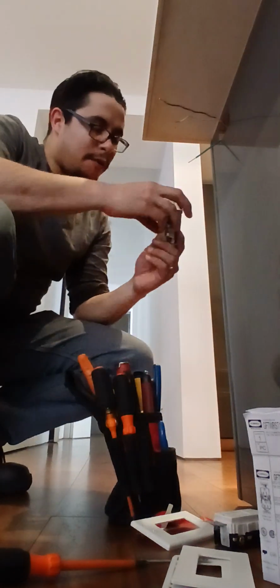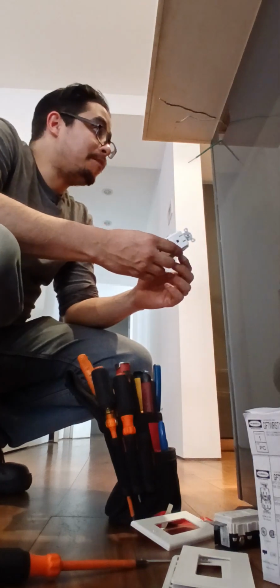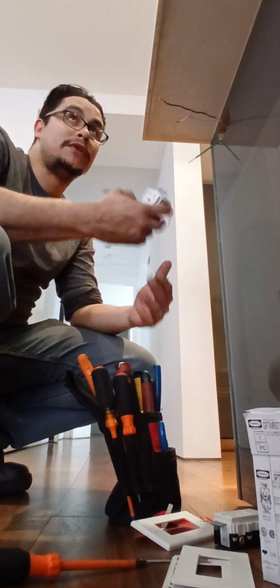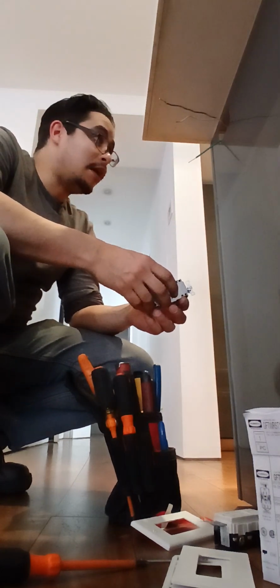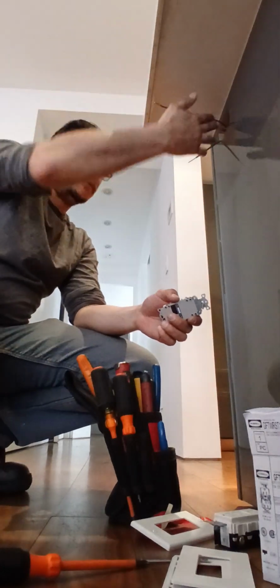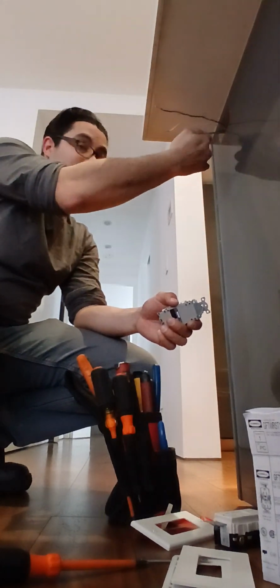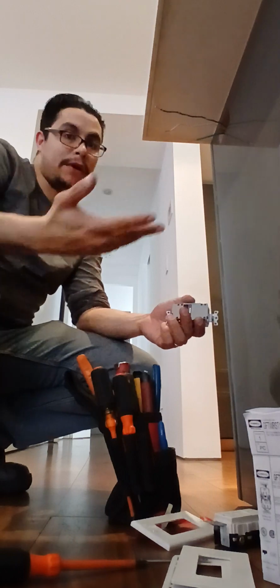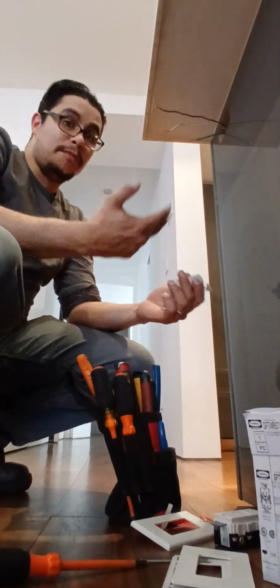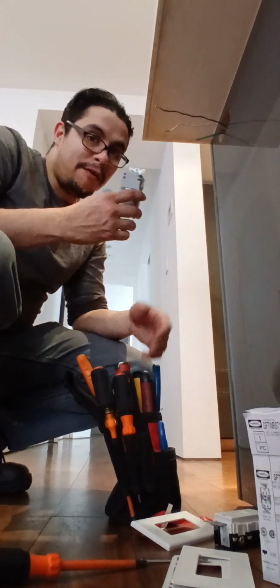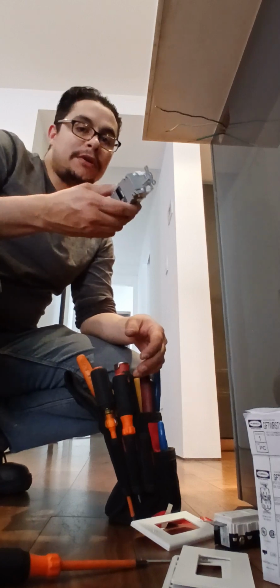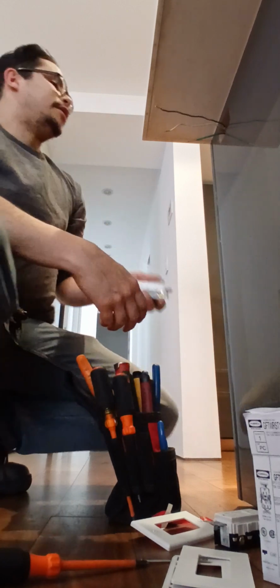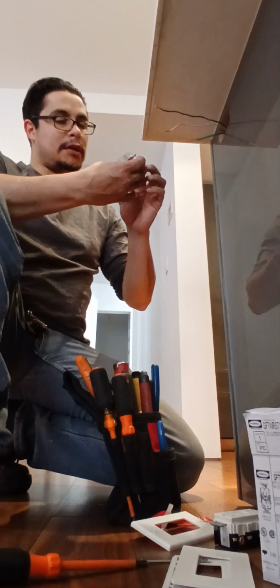In any case, this is the end of line, so obviously this is GFCI protected. What I mean by end of line is if there's 2 wires in the box, or just the equipment ground, or 3 wires if you have MC, and there's no pigtails or anything, that's your end of run circuit or end of run device.